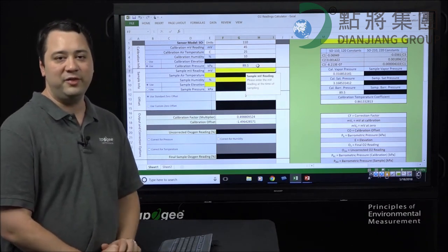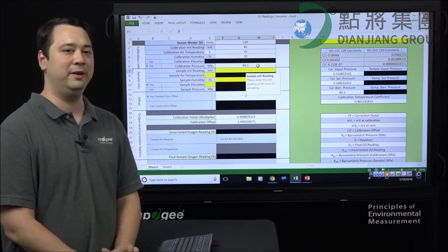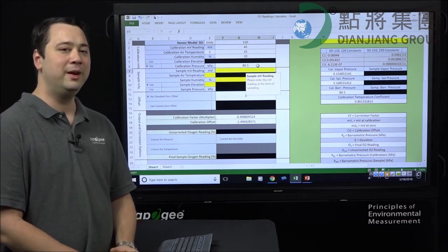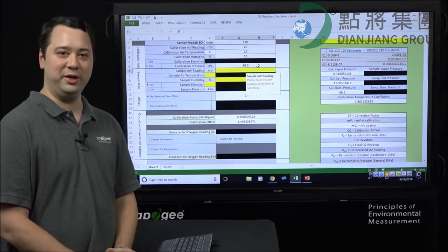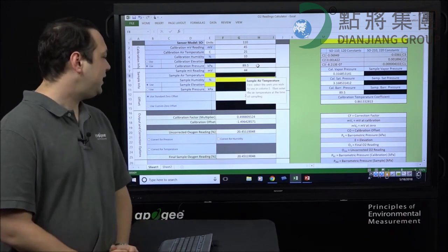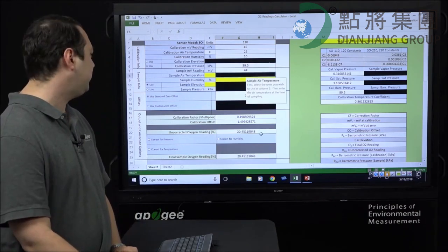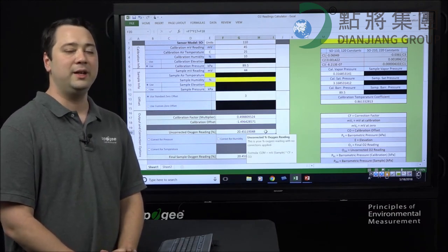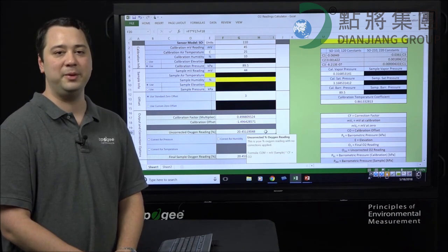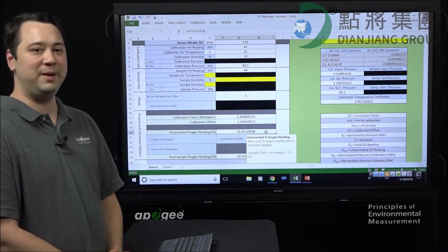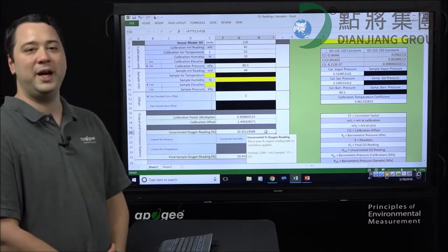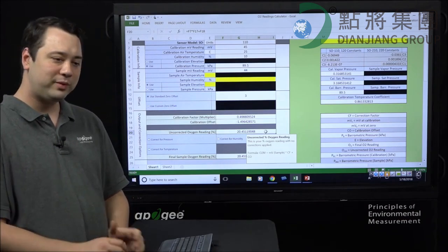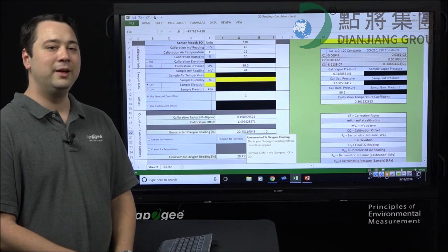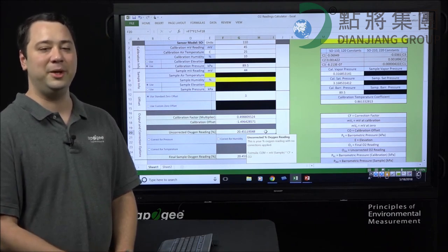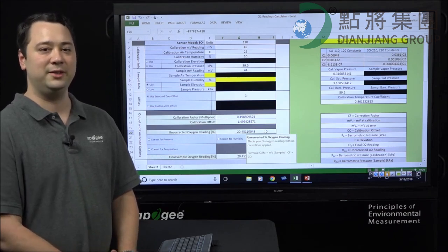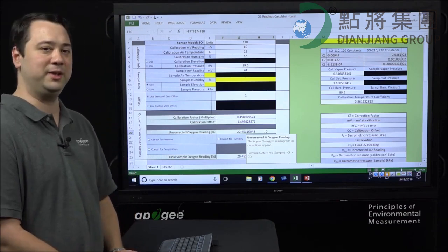Now that we have our calibration environment conditions entered, we can move on to our sample information. First, we'll want to start by entering the sample millivolt value, and let's go ahead and make up a value of 44 for this example. Now you can see the spreadsheet has already produced an uncorrected oxygen reading based on the information we gave it for the calibration readings and the sample millivolt reading that we just entered. Since that millivolt reading for the sample is a little bit lower, the oxygen reading reported by this spreadsheet is also lower at 20.4%. But it's important to remember this has not been corrected. So if the environment that you're sampling in is different from your calibration environment, the actual relative oxygen concentration will be different. So let's go ahead and apply those corrections.